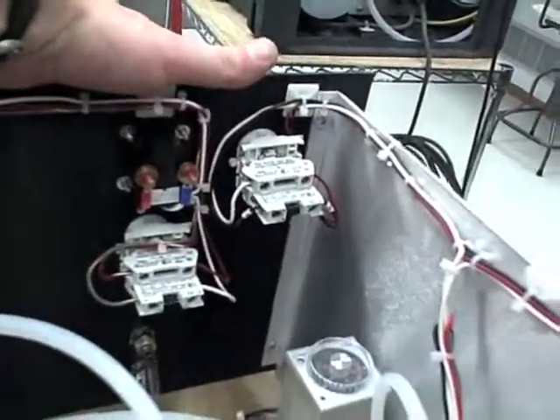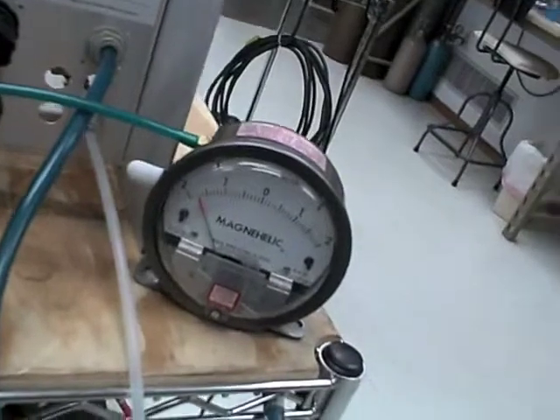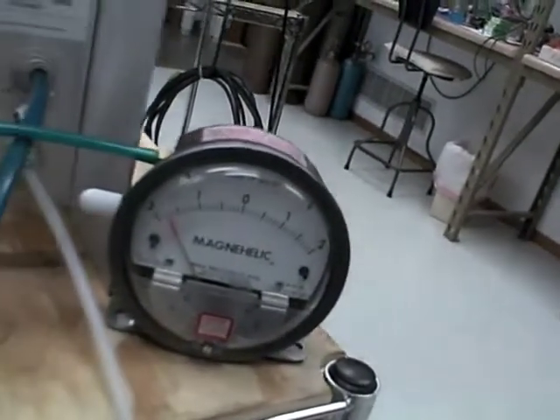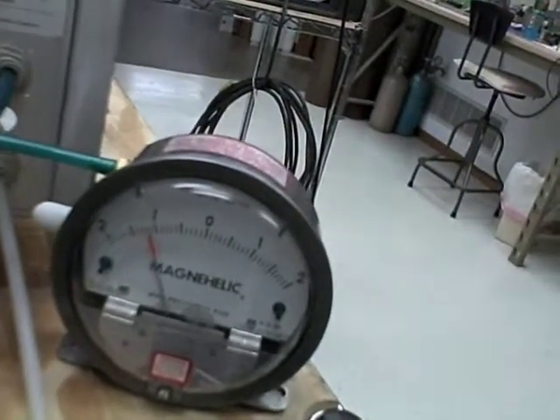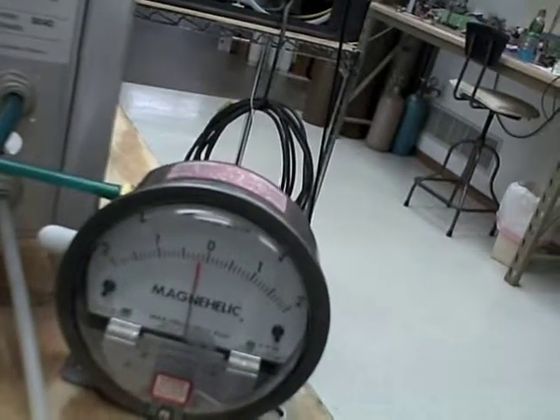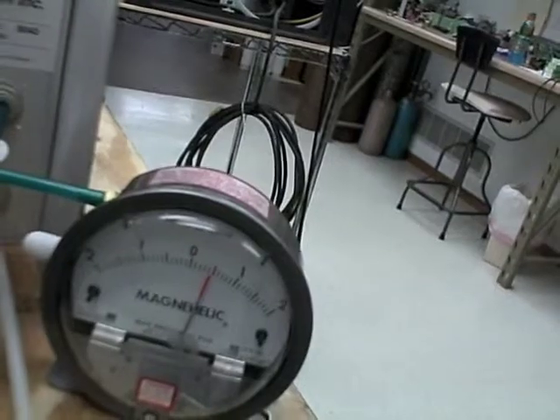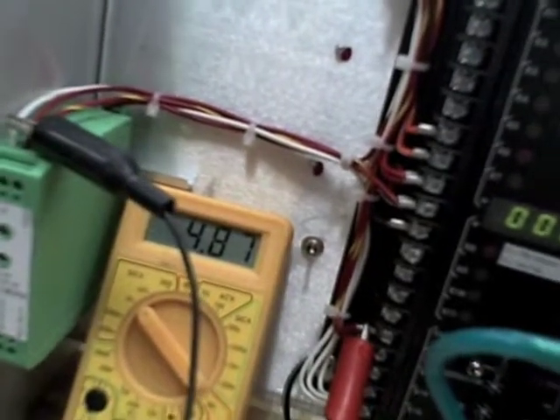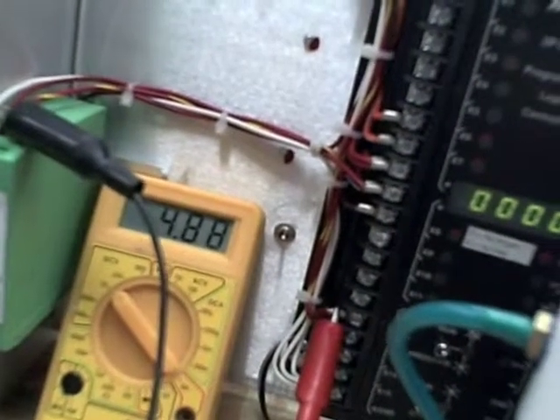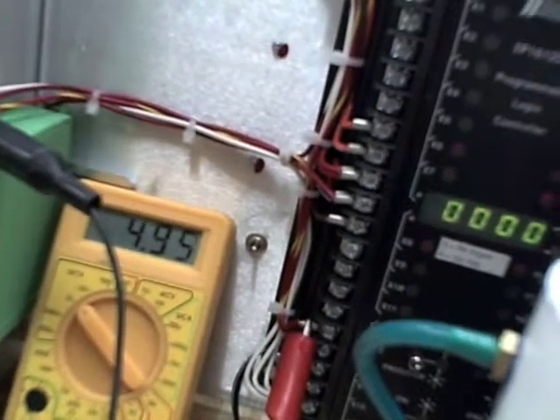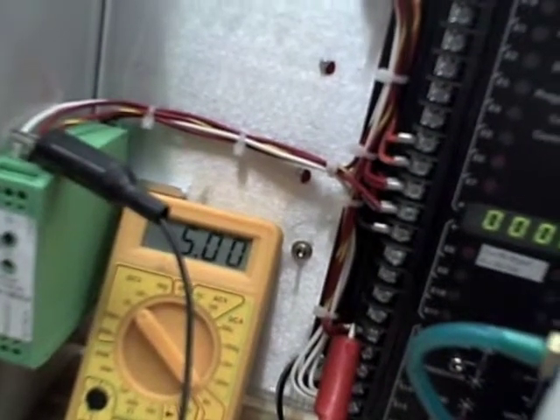And again, the sensor override switch is still in the up position. So I'm just going to reach around, hit the start button. We'll see that the Magnehelic reading is in the negative right now, and so the way that we would adjust that is by turning up the regulator until we get a half inch on the Magnehelic. And again, that half inch is just a nominal setting. As we get that half inch, now we can turn over and look at the voltmeter and wait for that to kind of settle down a little bit on a voltage. Pretty steady right there. So now we'll just take the screwdriver and adjust the gain screw till we get 5 volts. Okay, we got a 5 volts.